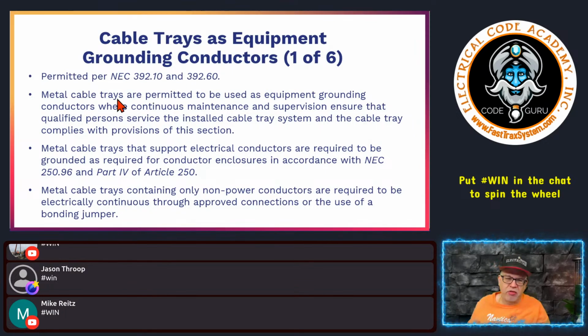It says metal cable trays are permitted to be used as equipment grounding conductors where continuous maintenance and supervision ensures that qualified persons service the installed cable tray system and the cable tray complies with the provisions of this section. So again, 392.60, it's got to follow all the rules in 392, and also any of the rules in Article 250 of the National Electrical Code. So we have a metal tray in a location under continuous maintenance and supervision. That's another thing. You cannot use the cable tray as an equipment grounding conductor in a location, even though we know it can be used in residential, commercial, or even industrial.